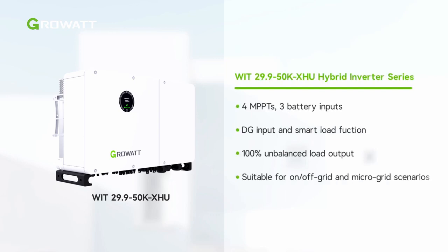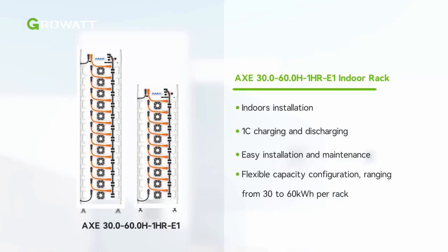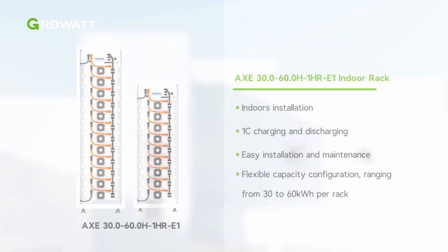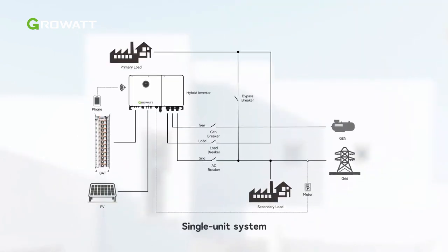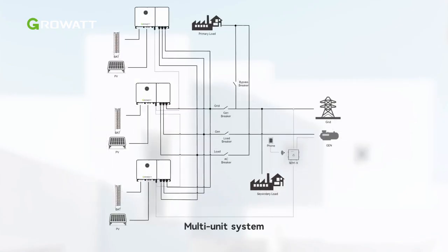As a robust C&I hybrid inverter, the WIT 29.9-50K-XHU inverter has various functions capable of fulfilling multiple application scenarios. The WIT-XHU inverter can be compatible with the AXE C&I battery system and installed as an indoor rack. The solution supports connecting up to 3 AXE racks to a single WIT-XHU inverter, covering battery capacity ranging from 30 to 180 kilowatt-hours.